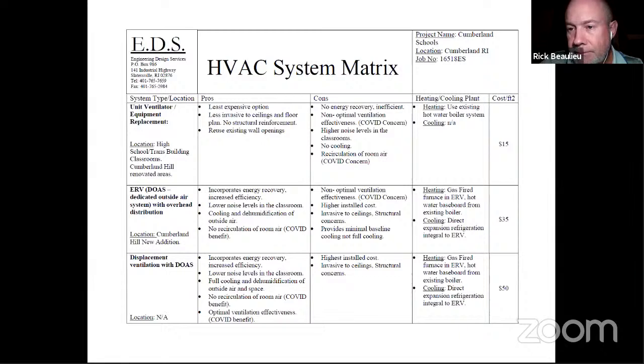Just my 2 cents on that - retrofitting the existing unit ventilators with higher efficiency filters, I think that's a possibility. Incorporating disinfection is also a pretty simple thing to do in a retrofit application. The air conditioning, we wouldn't be able to add a cooling coil into those existing unit ventilators.